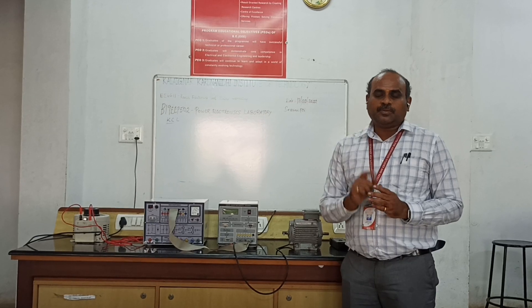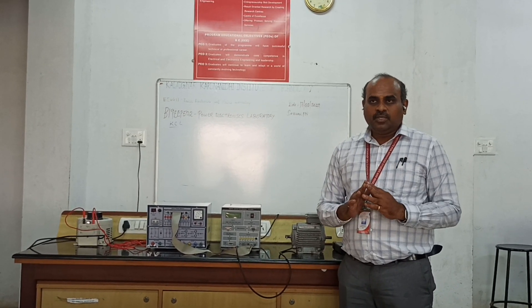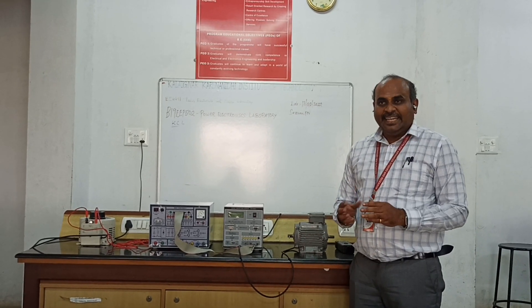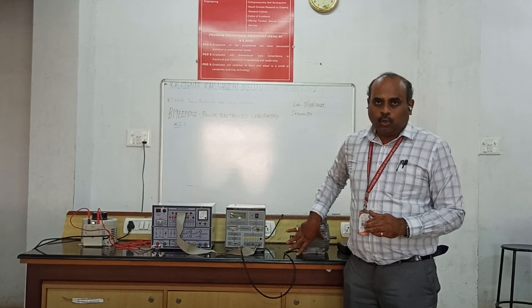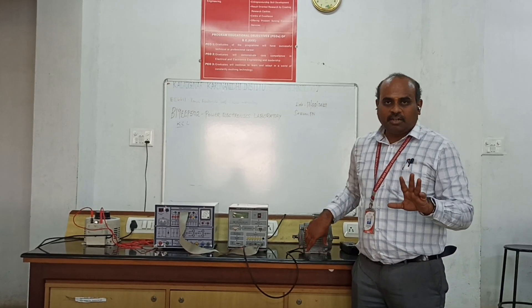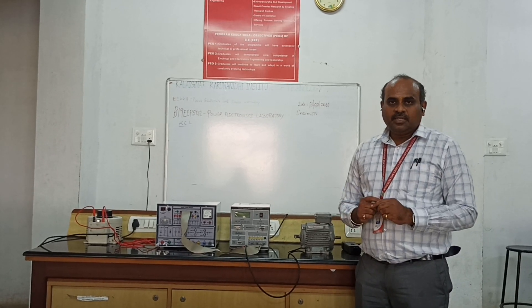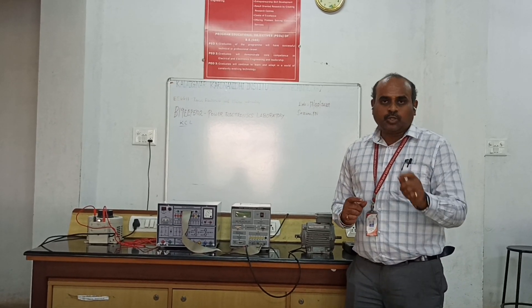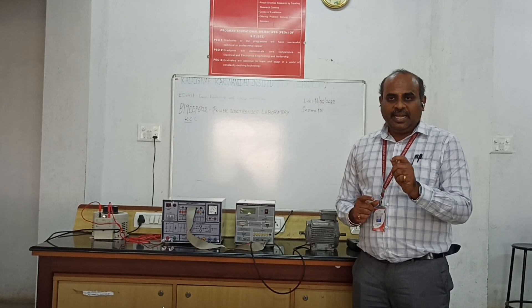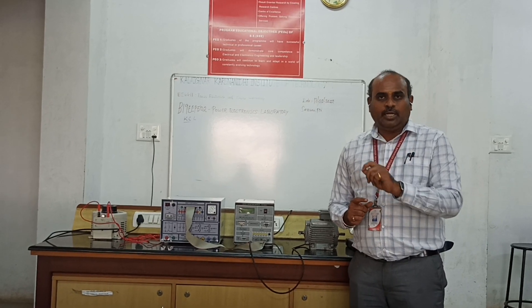As a result of the rotating magnetic field, EMF is induced in the rotor. The difference between the synchronous speed and rotor speed is called the slip speed. Slip is defined as: S = (Ns - Nr) / Ns, where Ns is synchronous speed and Nr is rotor speed. As a percentage, slip is multiplied by 100.